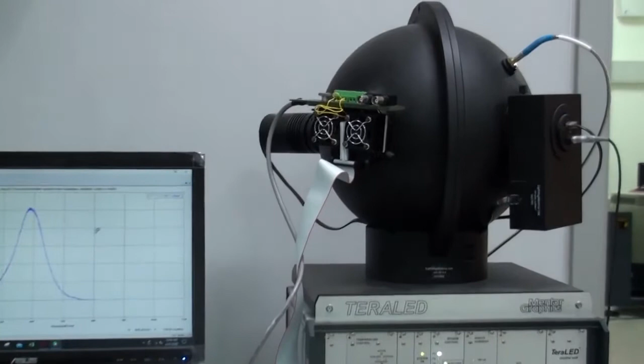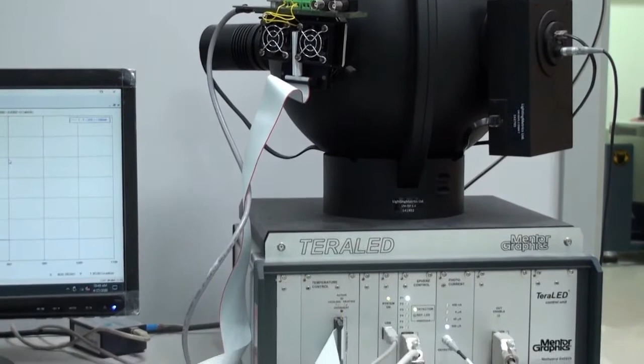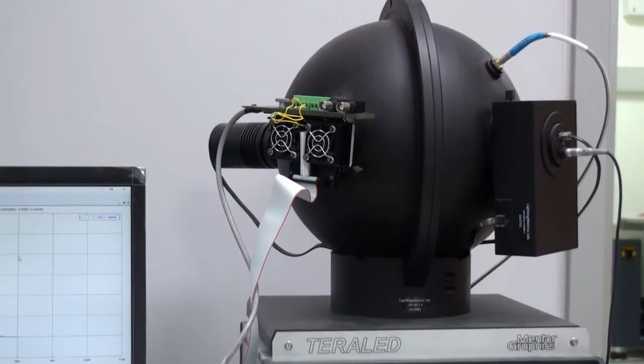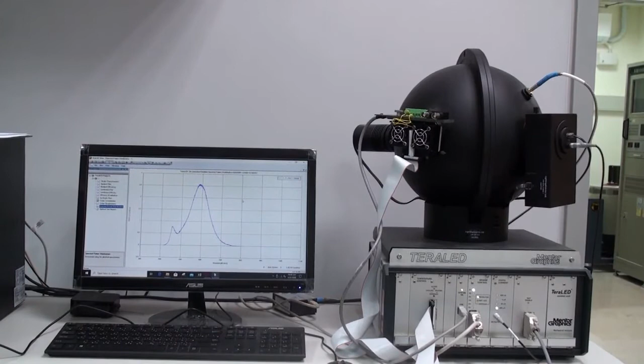This is a 30 centimeter integrating sphere from Mentor Graphics. The model is TeraLED. It measures optical characteristics such as color coordinates, luminous flux, radiant efficiency, luminous efficacy, radiant efficacy, and correlated color temperature for LEDs and solid state lighting arrays. The range for voltage is 0 to 5 volt and the current is 5 milliamp to 2 amp. It implements JEDEC standards such as JESD 51-51 and 51-52 compliant LED test setups. The temperature dependence of the light output parameters can be captured as the machine provides a temperature controlled environment during the measurements.